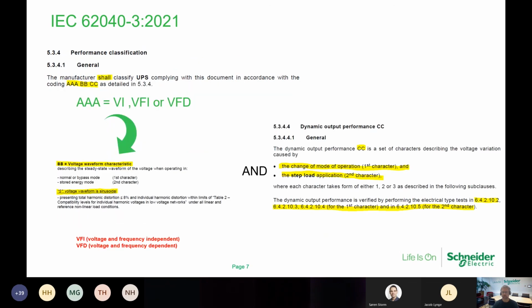Let's go to clause 5.3.4. The manufacturer shall classify the UPS according to the following coding: AAA, BB, and CC. The AAA is voltage and frequency dependent or independent. The BB is the voltage waveform. CC describes the voltage variations. The output performance is verified by some electrical tests on the system, according to clause 6.4.xx, which you can see at the bottom right side of your screen.